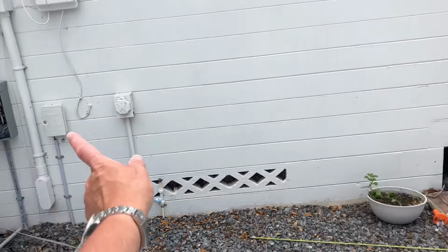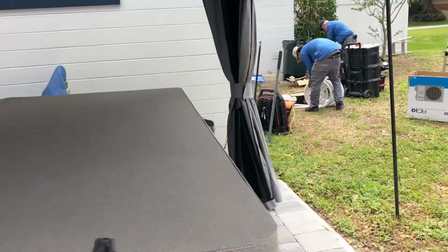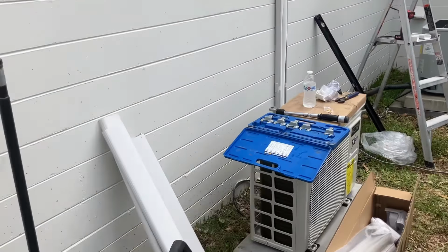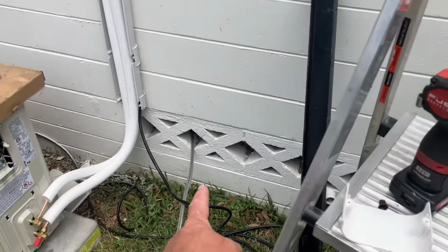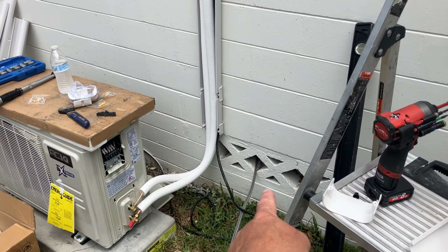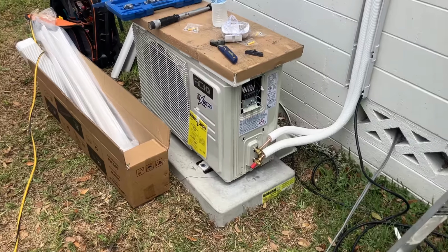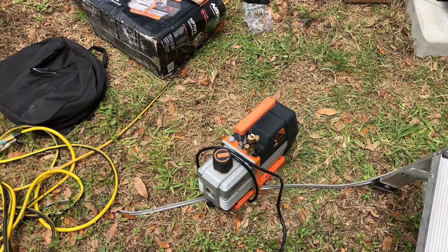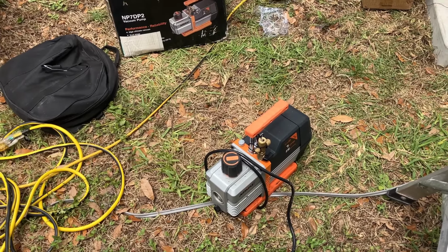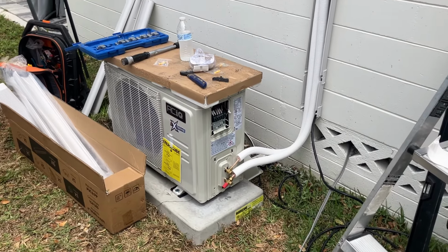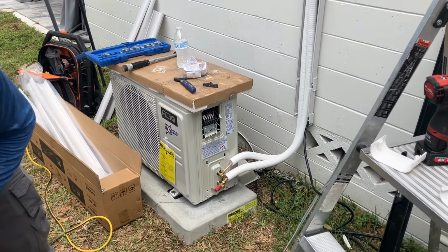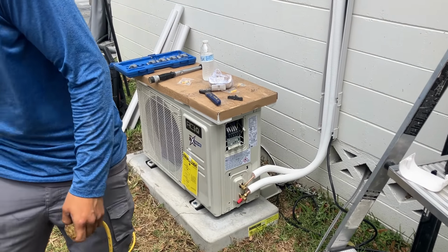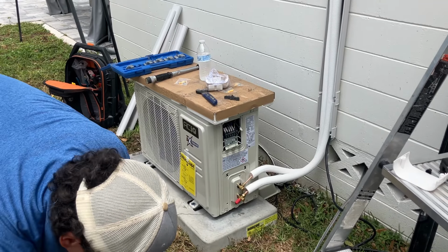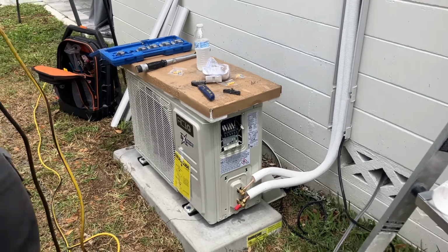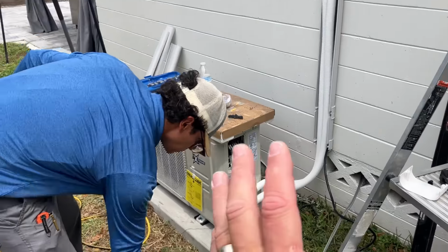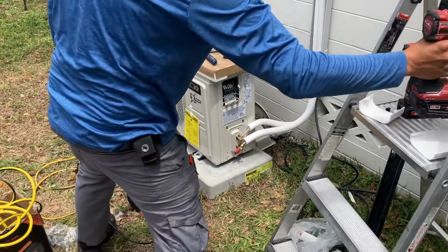He's running that circuit through the crawl space all the way to here, where we'll have our disconnect panel with surge protection, and we're about ready to pull down a vacuum using the NAVAC 7 CFM vacuum pump. We're going to pull a nice, tight, dry vacuum on this system, since moisture is the number one killer of compressors — that oil gets in there and fouls up the whole system. So no matter how great the install looks, you can mess it all up by not pulling a proper vacuum.